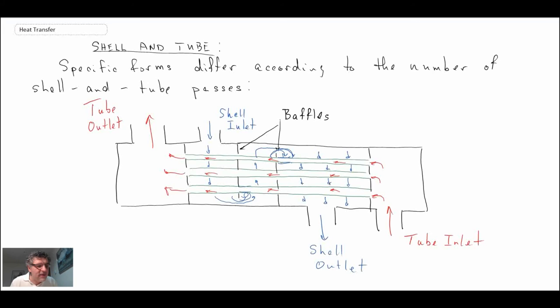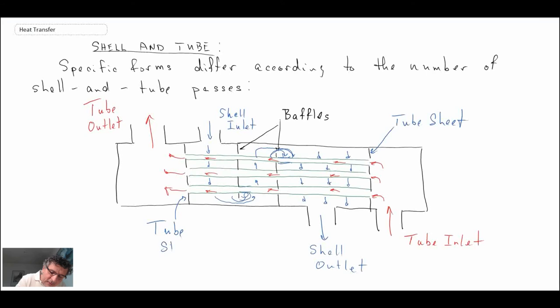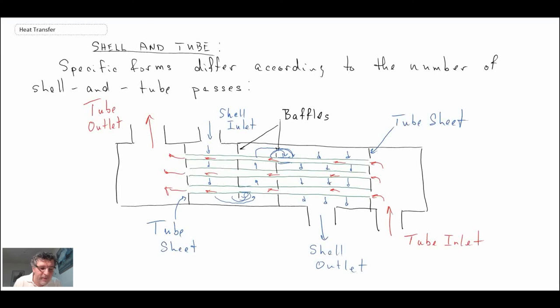Different baffle designs can be used to enhance mixing. The construction also includes a tube sheet on each side — that is where the tubes come through and are usually welded. The baffles are typically not welded; they are free to move. You want baffles to minimize flow-induced vibration and to force the shell-side flow around the tube bundle multiple times.